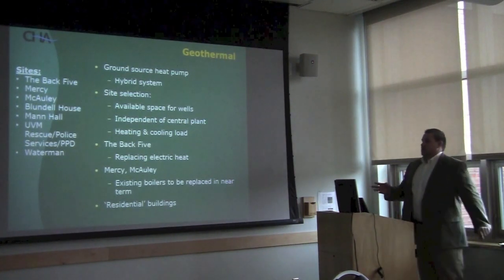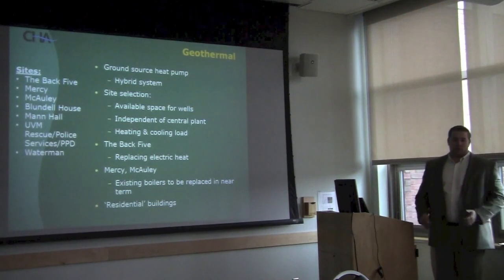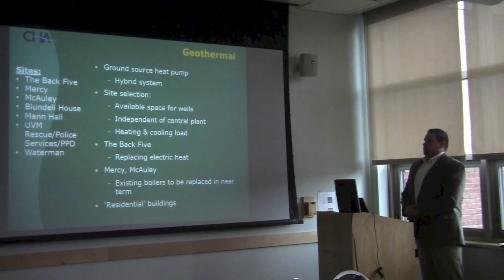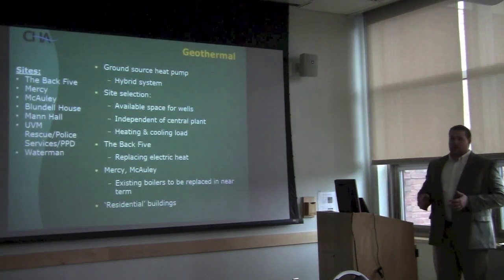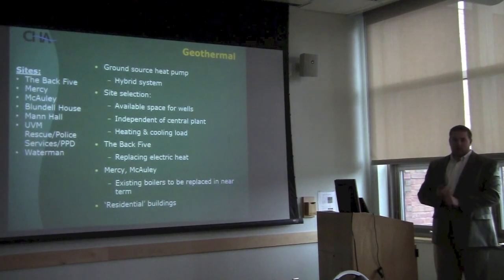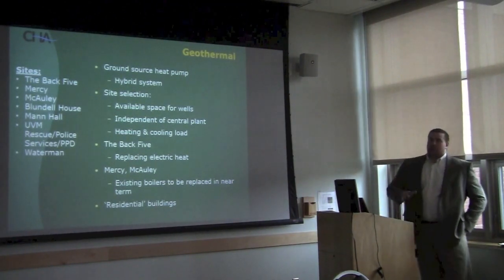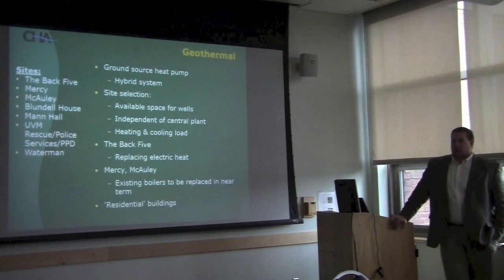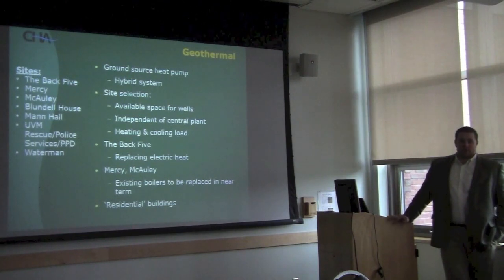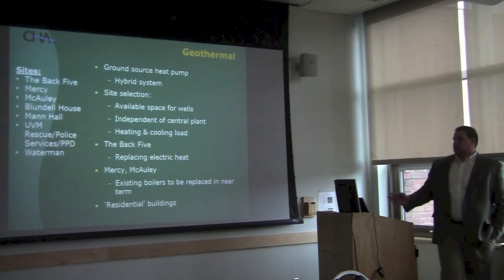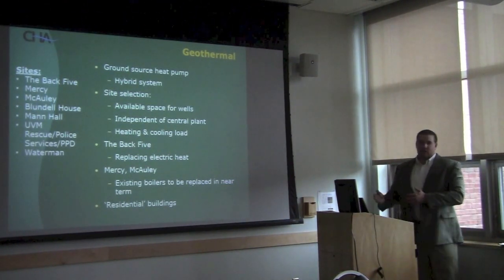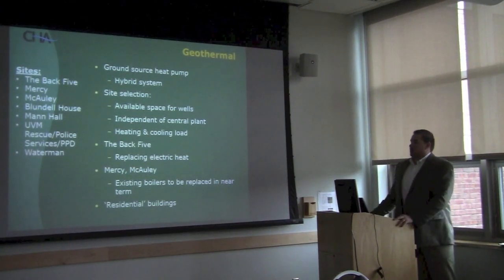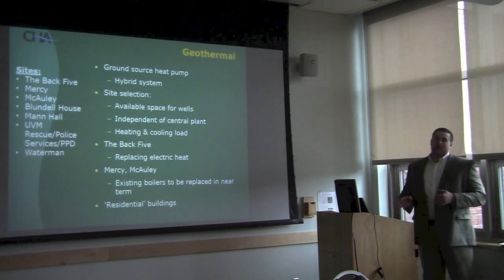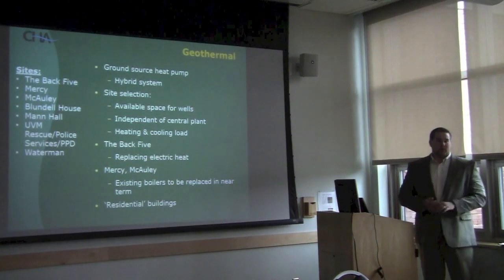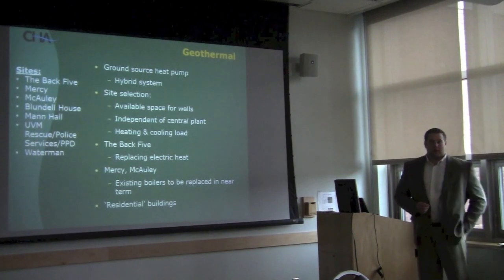Replacing them with a hydronic natural gas boiler augmented with geothermal would possibly make sense in that case too. On the back 5, you'd be replacing all of the building's heating infrastructure, adding a natural gas boiler augmented with geothermal. Typically we see up to 30% savings versus traditional heat. We weren't able to do a full economic analysis for geothermal at this time, because the costs largely depend on how much piping we're required to replace, and we need more information. But considering the back 5 and Mercy McAuley, natural gas heating and cooling augmented with geothermal would be competitive with an extension of the steam system, and certainly competitive with the biomass options identified before.